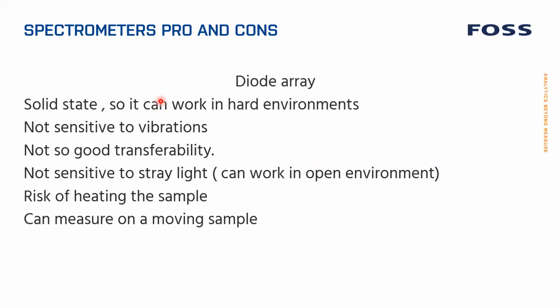So it's solid state, nothing moving, so it can work in really hard environments. It's not sensitive at all to vibrations. One of the drawbacks is it doesn't have so good transferability, because resolution is lower than you have on the monochromators. It's not sensitive to stray light, so it can work in an open environment. So if you have a conveyor belt or something like that, it can work there.